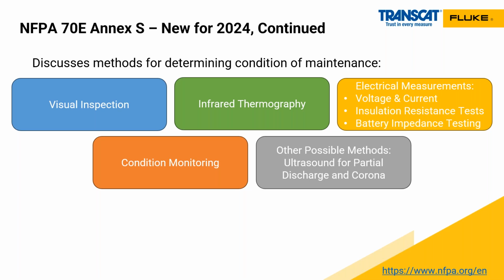For those who don't know, partial discharge is literally the breaking down of electrical insulation. Traditionally it's on a higher power circuit, but could be on high voltage circuits like in a switch substation or switchgear. A corona is kind of this noise component of electrical arcing. It's almost a precursor of a future failure. If two arcs join, bad things happen. So we can use this to determine that we have breakdown of this insulation and fix and repair this before we have an actual outage or electrical fault.